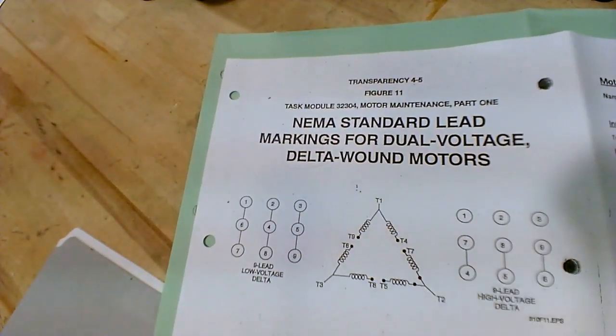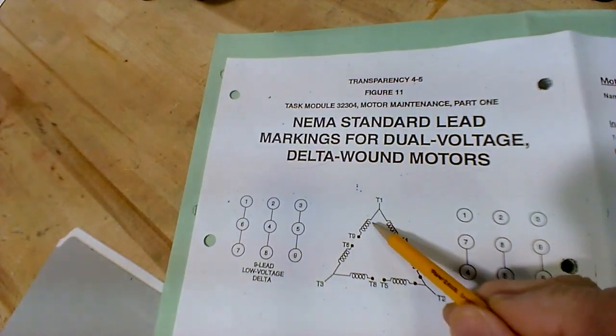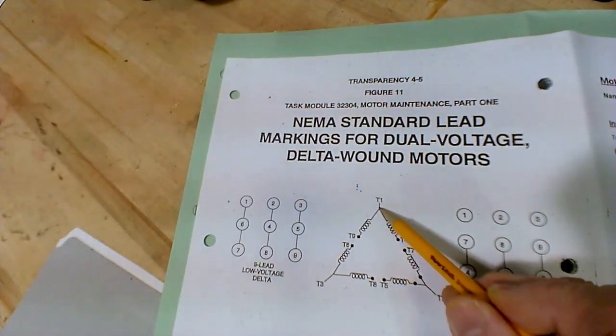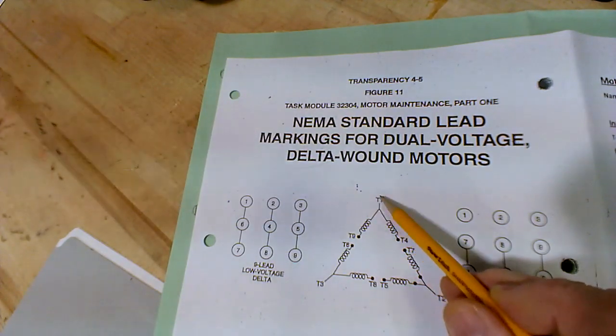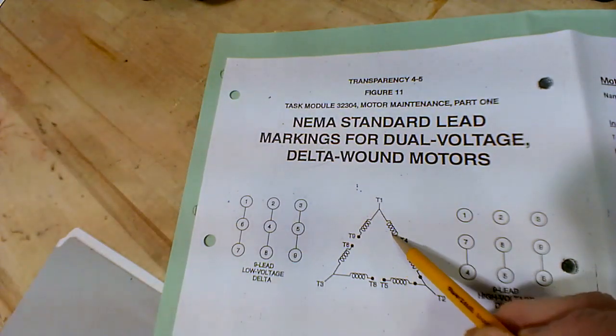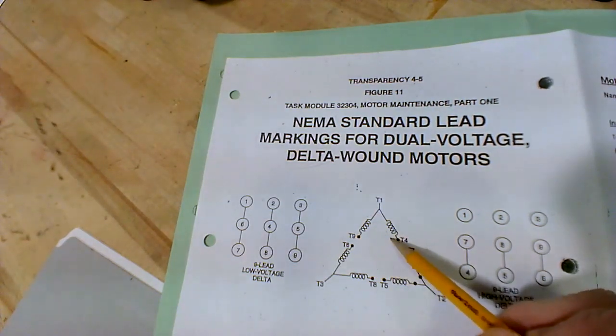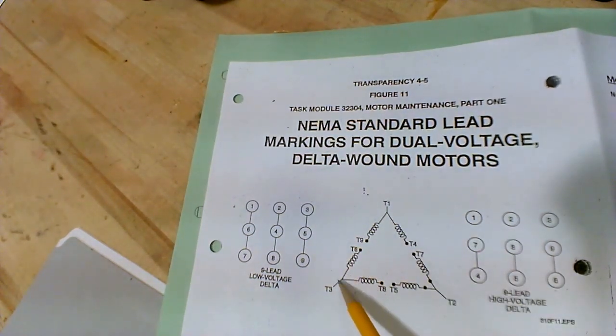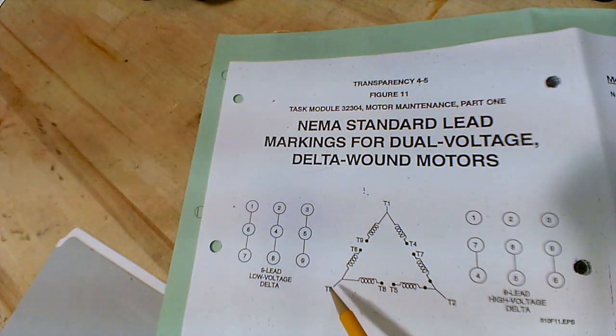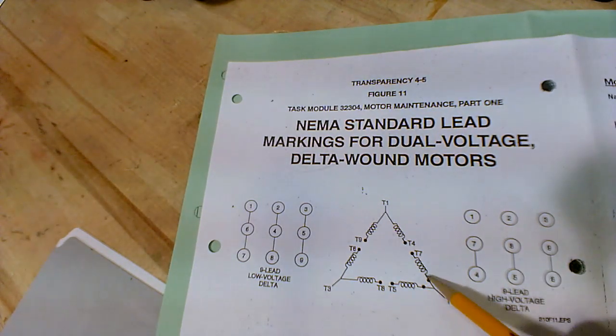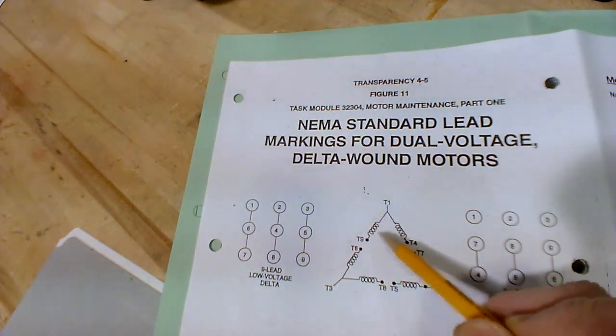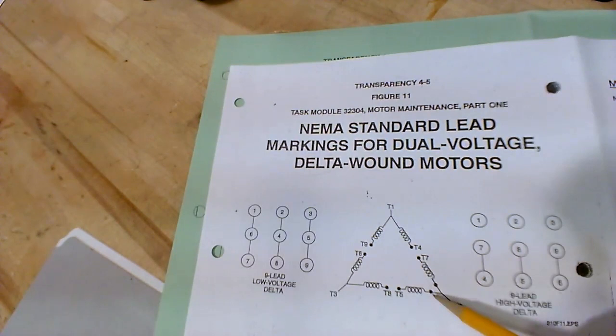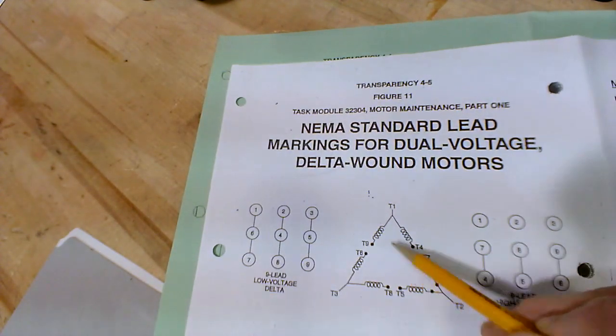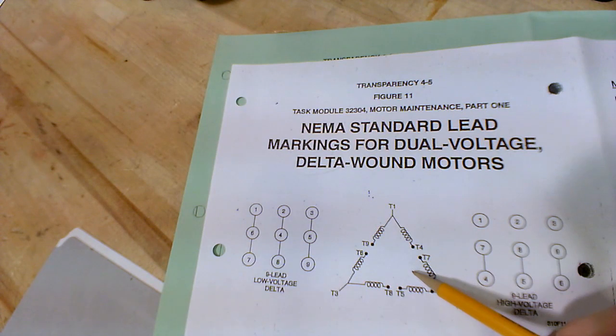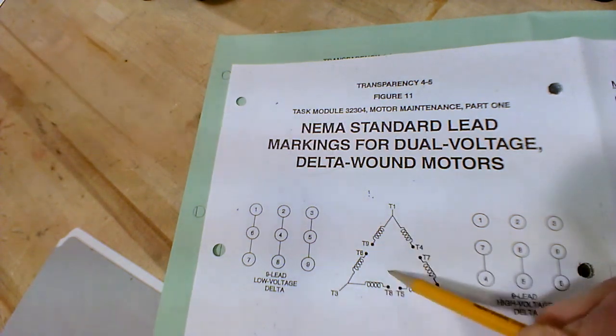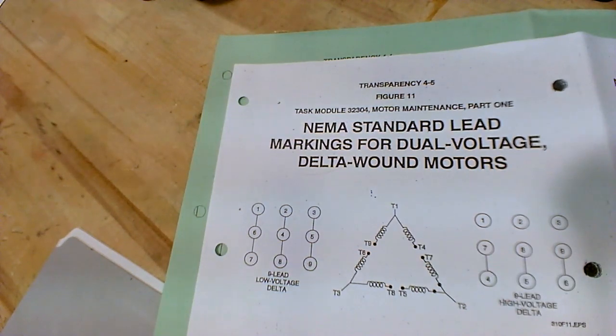On the delta, there's no Y connection built in, but here's what you do have. You've got these 2 windings connected internally. So the T1 lead that comes out of the motor, it's already hooked up the 2 ends of these coils. And then these ends are free for you to do whatever you're going to do with it over here. These 2 ends are tied together already to the T3 lead coming out of the motor. These are already hooked together permanently. So you've got some connections there that are already permanently done in the motor. You can't change them. And overall, the configuration looks like a triangle inside that motor, and it's called delta. That's a Greek symbol. Delta is a Greek symbol. That's what they call it.